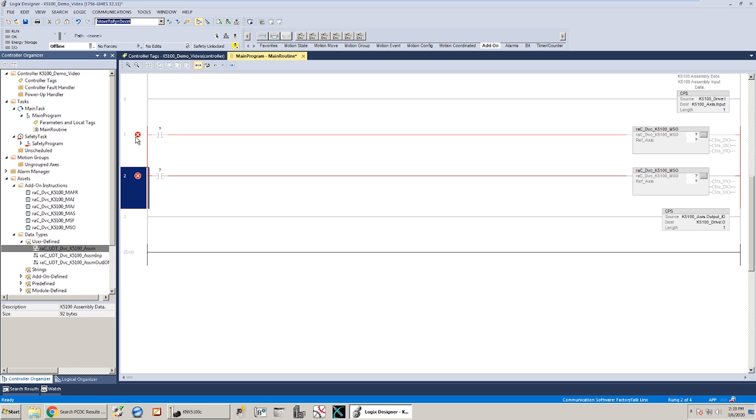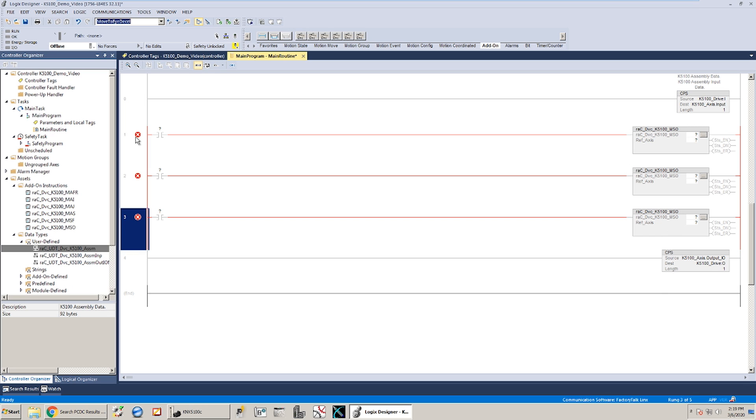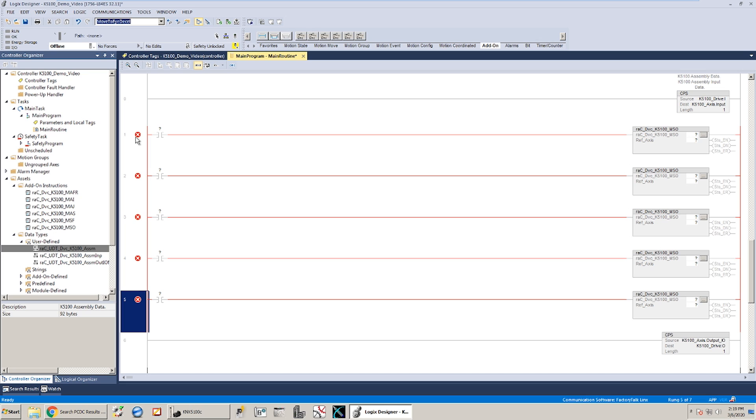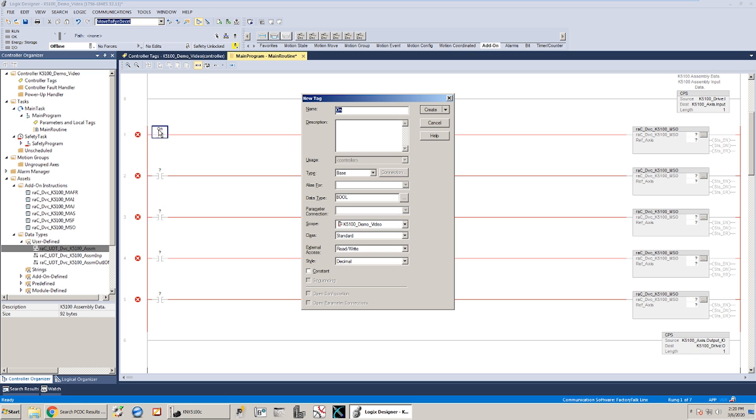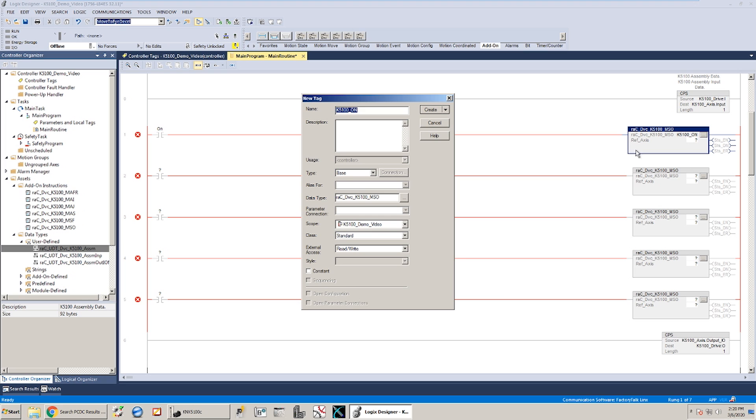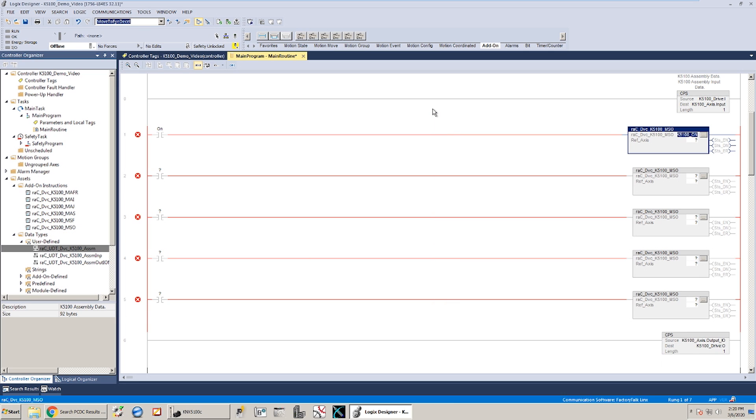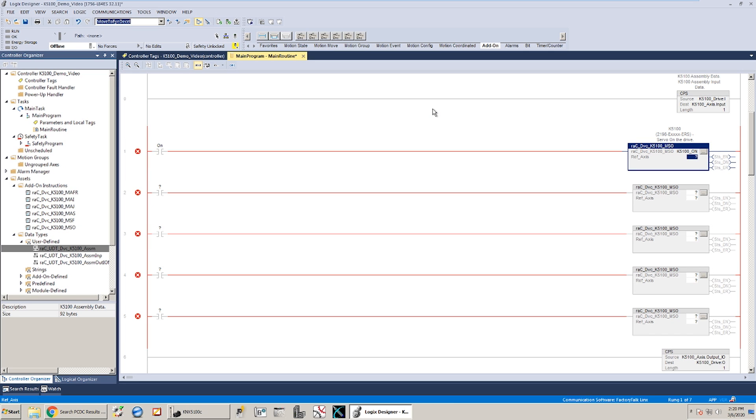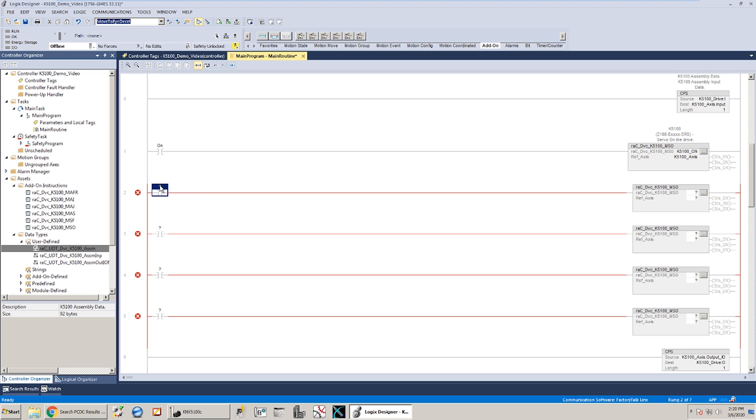I'm going to close in front of that and I'll kind of take that same structure and run with it. I'll have an on and off, a jog, a stop, maybe a fault reset and that'll be good for the sake of this demonstration. So I'll make a bool here so I can toggle this on, and this first piece that we have to enter in here on the motion servo on block is kind of like using a motion instruction tag. There's a specific one for each one of these blocks, but if I just type in say K5100 on for instance, this is an example of a tag name. Make a new one, you'll see that the data type is pre-populated by creating it on that MSO block, it knows what that data type needs to be. I say create and then the reference axis is going to be that K5100 axis.